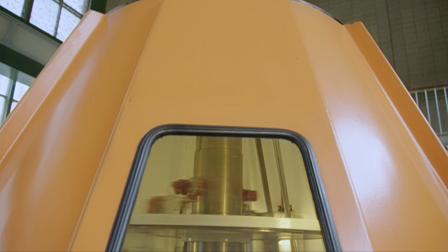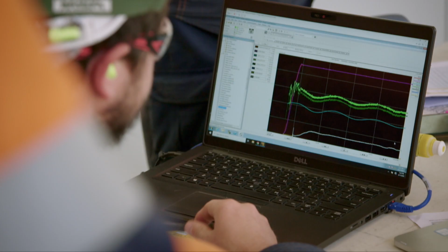So we've just finished our first test and we've got an issue with the unit lifting up by 1.3 mils. And we're worried that if the unit was in service and we had a trip at 95 megawatts, the unit would lift up a little bit higher, up to about 2.5 mils, and we could come in contact with one of our covers. So that's why we've been doing this test, and we need to tune the pressures around the turbine so it doesn't rise that much.